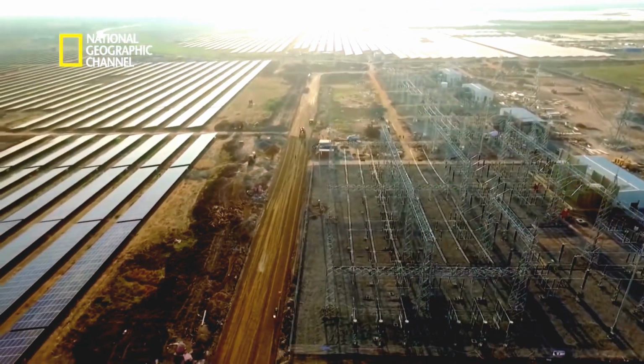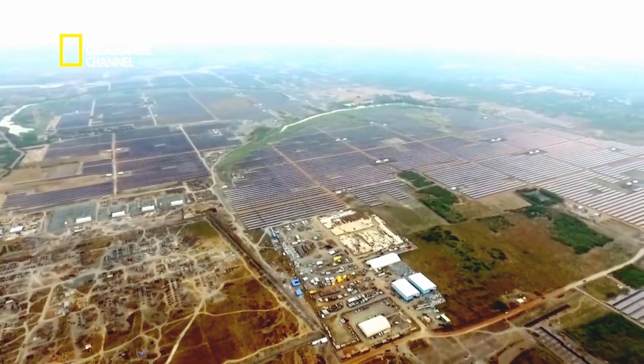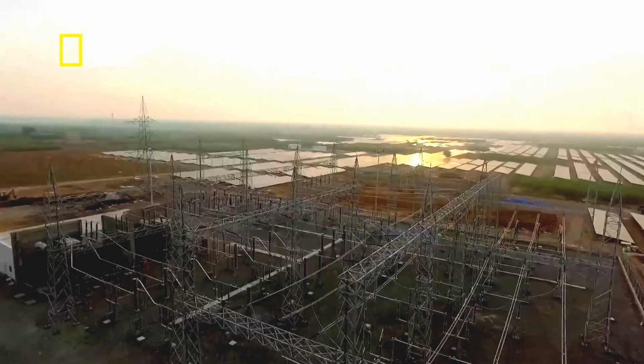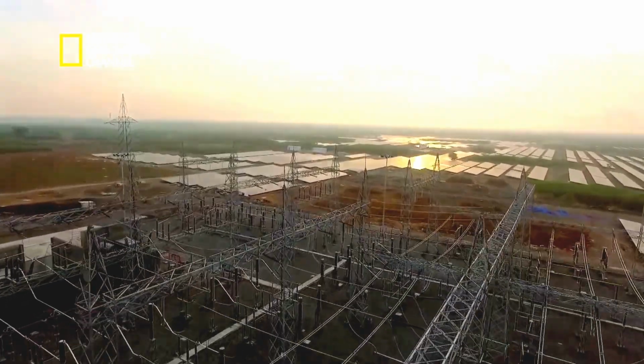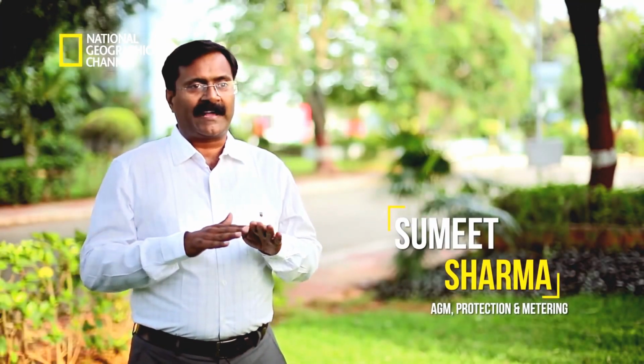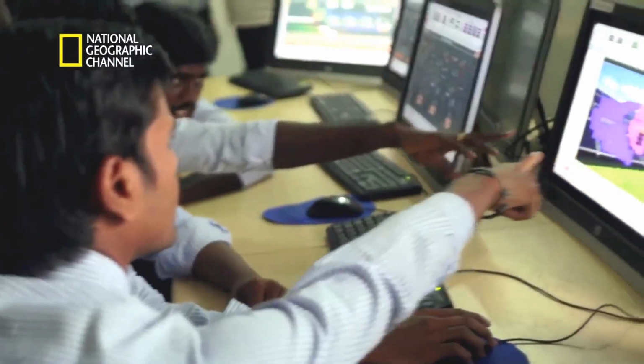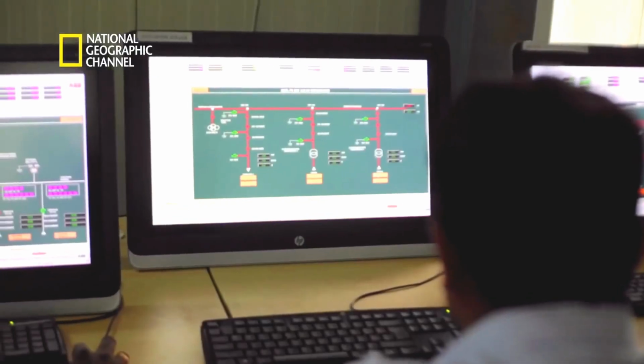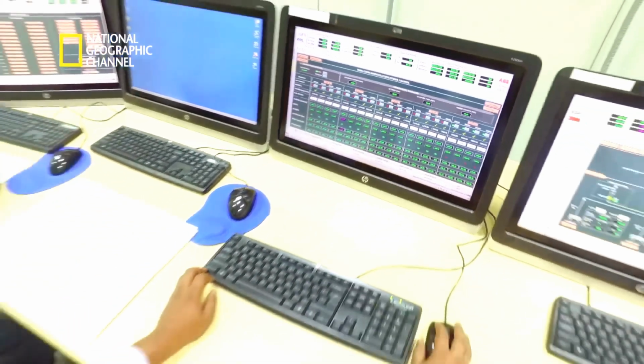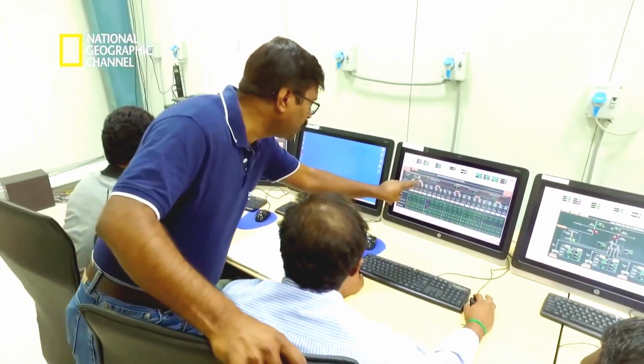Since we are building a very huge solar plant of a scale of 640 megawatts, the fluctuation in our solar plant will actually affect the grid operations. In that case, the grid operations will request us to maintain the power of the plant at a fixed output. So you need an aspect in the SCADA system, in the control automation systems, which can help you do that function.